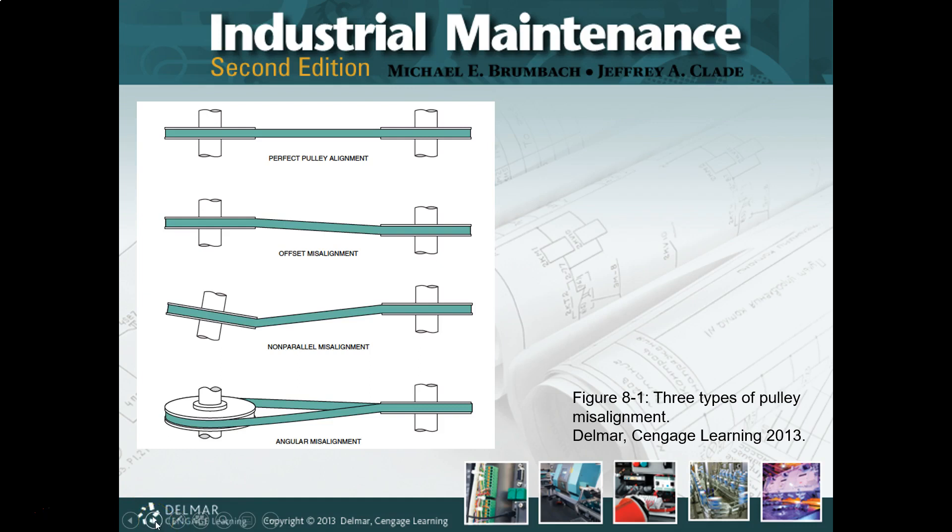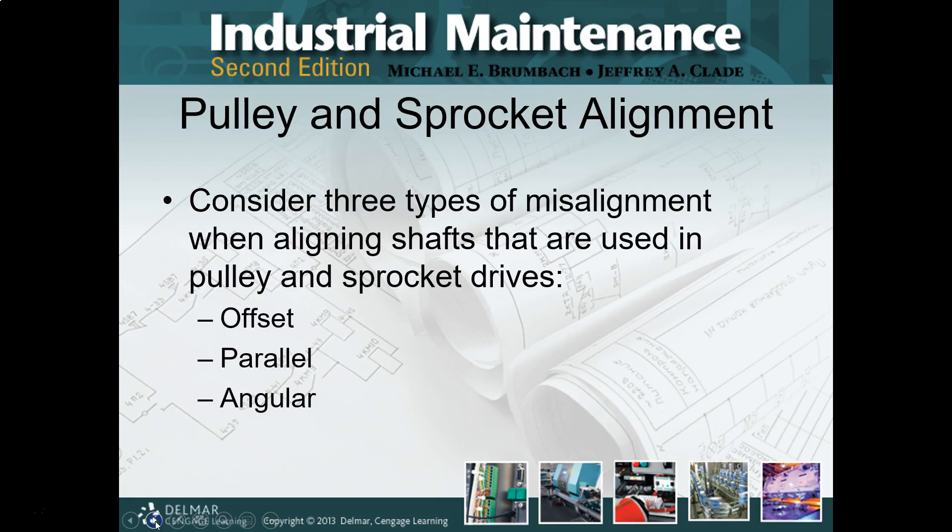The fun news is that typically it's offset — that is the biggest one. Trying to get the pulleys and sheaves all in the same plane. If you over-tighten or put too much tension on the belt, you usually start getting into the non-parallel misalignment. Just so you know.